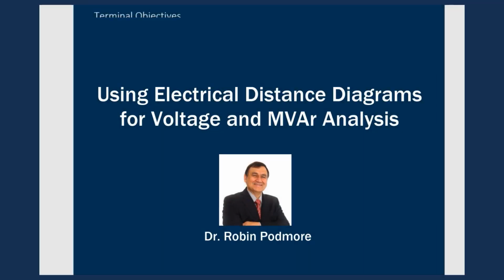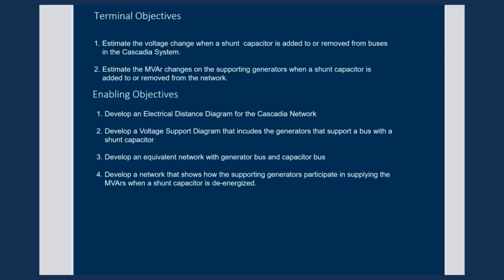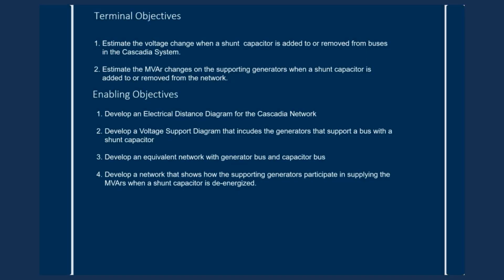Welcome, I'm Robin Podmore. The title of this module is Using Electrical Distance Diagrams for Voltage and Megavar Analysis. The terminal objectives for this session will be, firstly, to estimate the voltage change when a shunt capacitor is added to or removed from buses in the Cascadia system. Secondly, to estimate the MVAr changes that will occur on supporting generators when a shunt capacitor is added to or removed from the network.